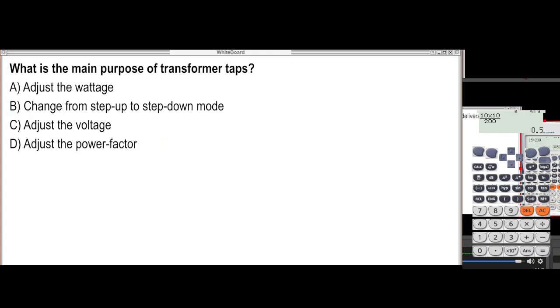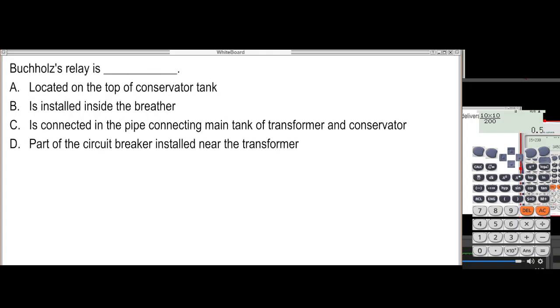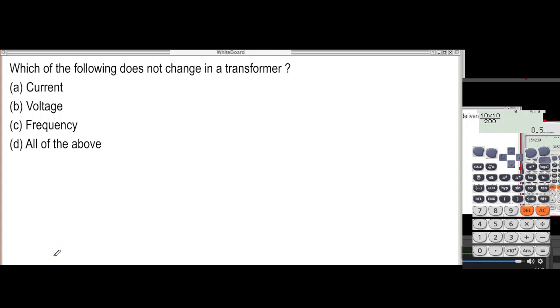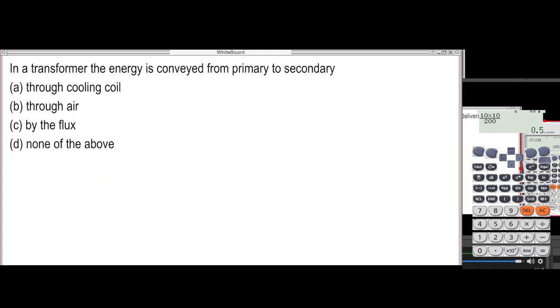What is the main purpose of a transformer tap? That is to adjust the voltage. Tapping the transformer is used to adjust the voltage. The Buchholz relay is usually connected in the pipe between the main tank of the transformer and the conservator. Which of the following does not change in a transformer? By the definition of a transformer, its frequency does not change. In a transformer, the energy is conveyed from primary to secondary through the flux.